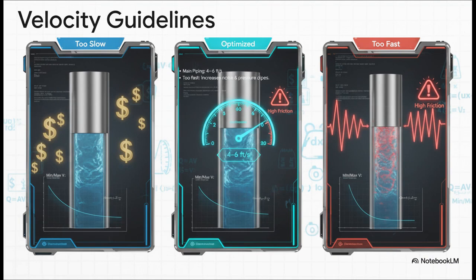This is kind of like a Goldilocks problem. There are industry standards that give us a target. For the main pipes, you're aiming for a speed of about 4 to 6 feet per second. If you go too fast, the system gets noisy and you waste a ton of energy on friction. But if you go too slow, you need much bigger pipes, and that gets really expensive really fast. The engineer's entire job is to find that just right sweet spot between saving energy and saving money on materials.